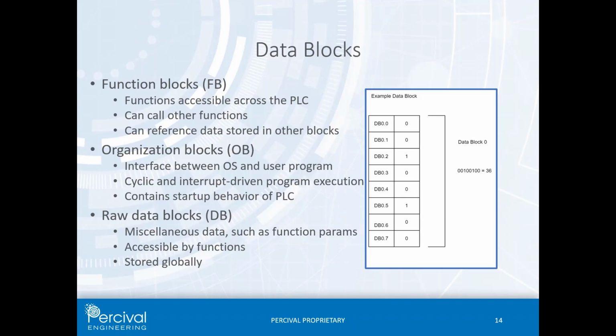These can be characterized as function blocks, organization blocks, or raw data blocks. Function blocks are accessible across the PLC, and as the name implies, they will store PLC functions. PLC functions may reference data stored in other blocks, and they can even call other function blocks.